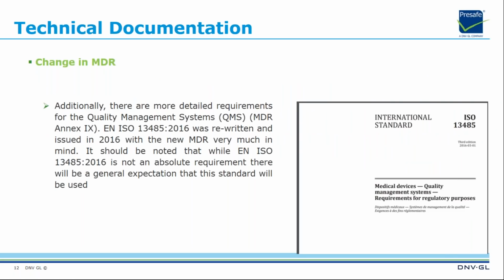On the other hand, there are more detailed requirements for the quality management system based on requirements of ISO 13485. The 2016 edition was rewritten and issued in 2016 with the new MDR very much in mind. It should be noted that while EN ISO 13485 is not an absolute requirement, there will be a general expectation that this standard will be used.